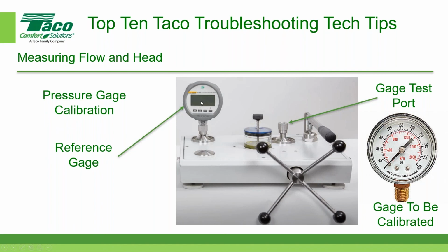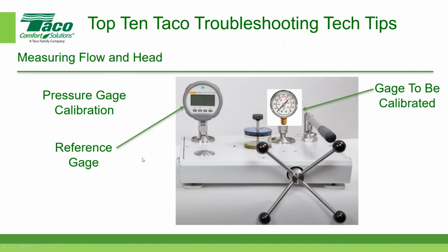So if you wanted to calibrate this gauge, you would crank these pressure valves up until the reference gauge read, for example, 150 PSI, and that's what should read on the actual gauge. And then there are adjustments that can be made, which can be done by the gauge supplier or gauge manufacturer. So it's fairly simple and straightforward to get a calibrated gauge. And that's how you do it. Like I said, you connect the gauge, you put in the pressure on the reference, and then you adjust the actual gauge to give you the reading that you're looking for.